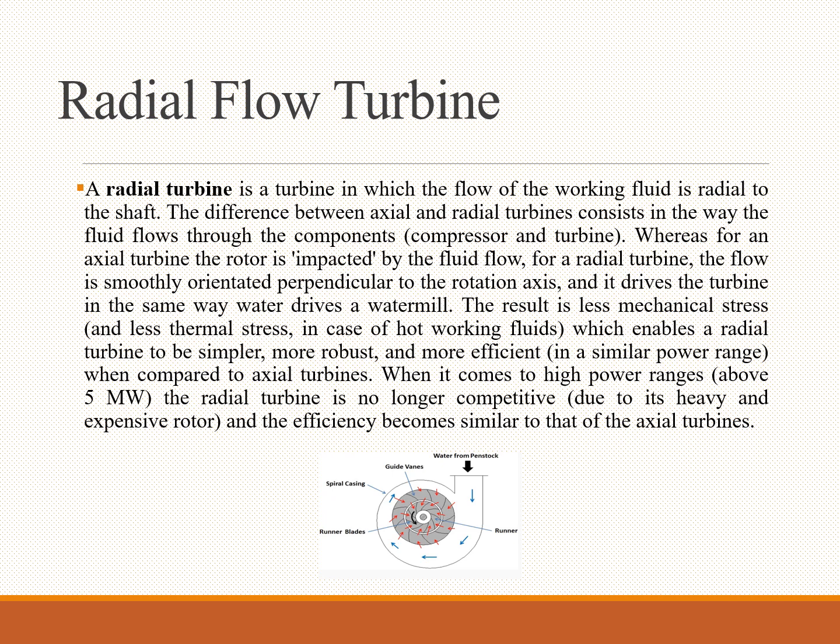The result is less mechanical stress and less thermal stress in the case of hot working fluids, which enables a radial turbine to be simpler, more robust and more efficient in a similar power range when compared to axial turbines. When it comes to a high power range above 5 MW, the radial turbine is no longer competitive due to its heavy and expensive rotor, and the efficiency becomes similar to the axial turbine.